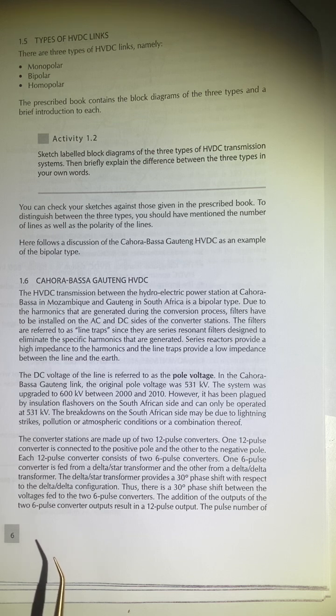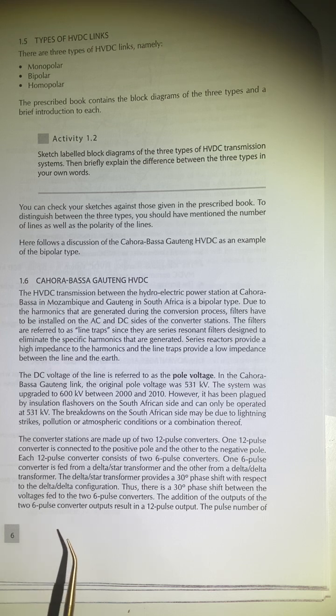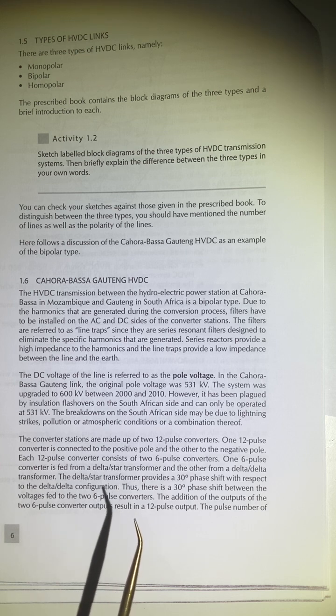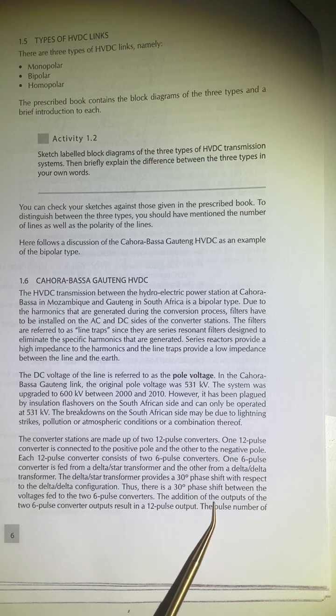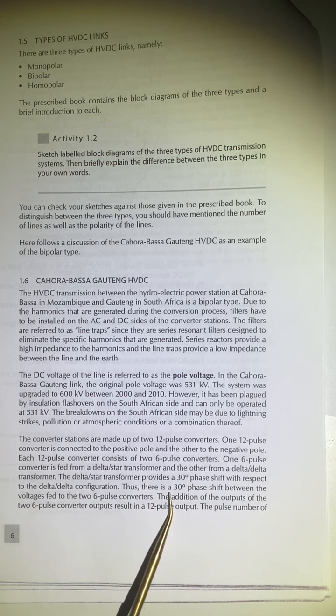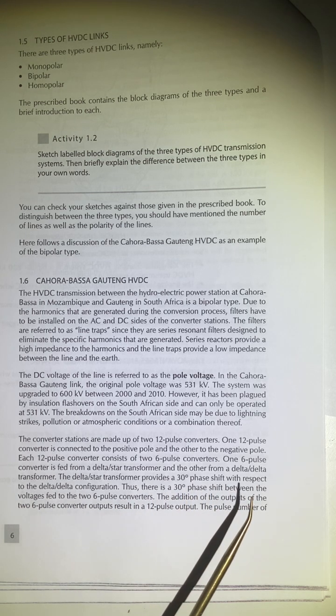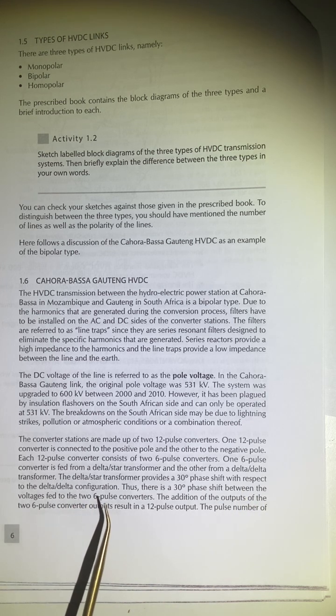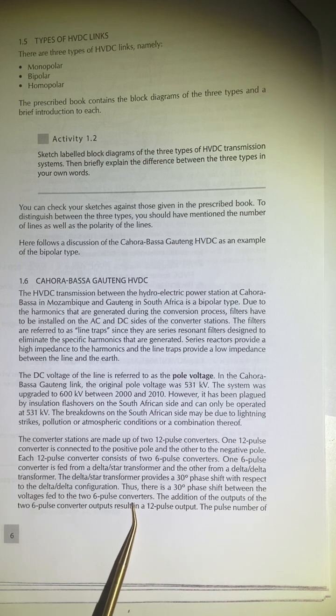If you have a delta-star or a star-delta configuration, there will be a 30-degree phase shift. Thus, there is a 30-degree phase shift between the voltages fed to the two six-pulse converters.